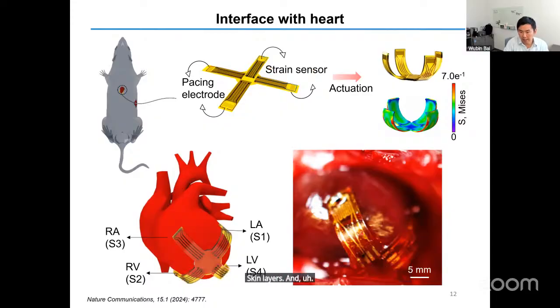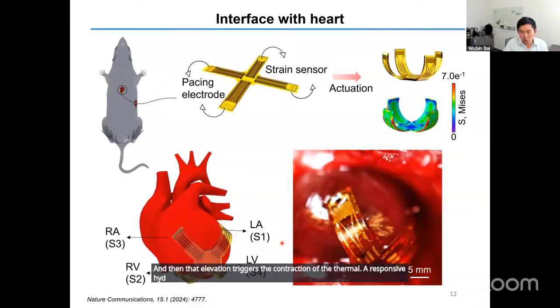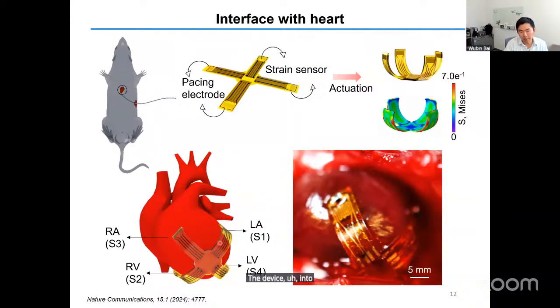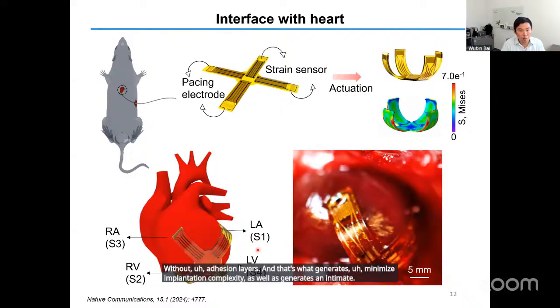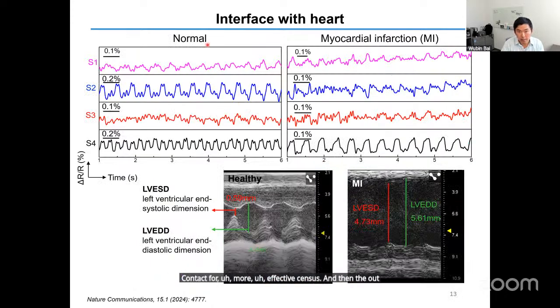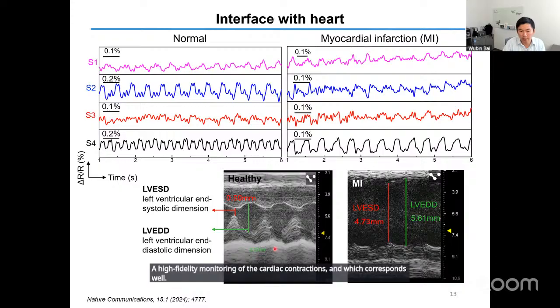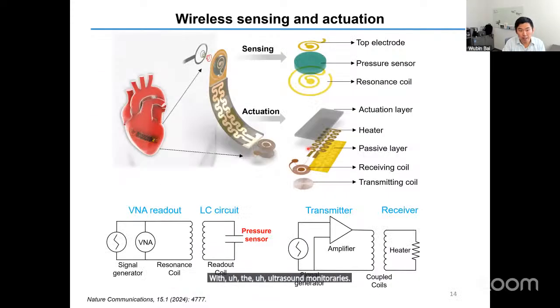And upon contact with the tissue, which will elevate the temperature of the device, that elevation triggers the contraction of the thermal responsive hydrogel in order to bend the device into a bowl shape that can hold the heart by itself. As you can see from the picture, without additional interventions, the device can physically hold the heart without adhesion layers. That minimizes implantation complexity as well as generating intimate contact for more effective sensing. And then the outcome is high fidelity monitoring of the cardiac contractions, which corresponds well with the ultrasound monitoring. And then you could imagine how we can make the implant operate wirelessly.